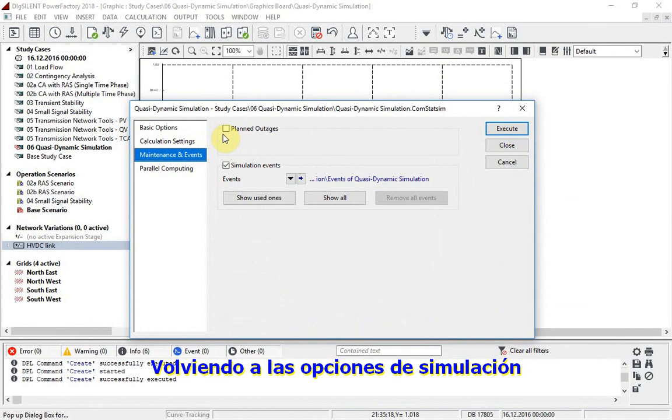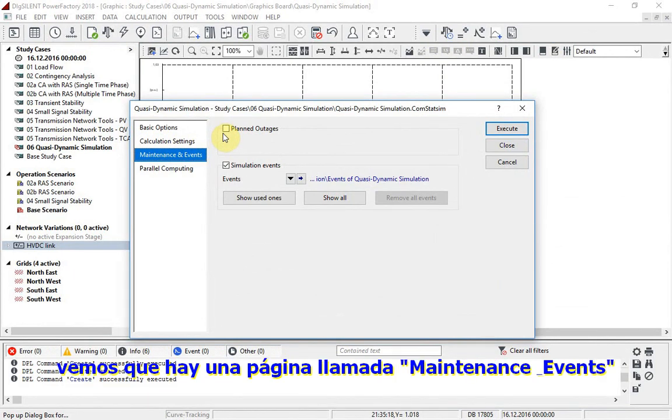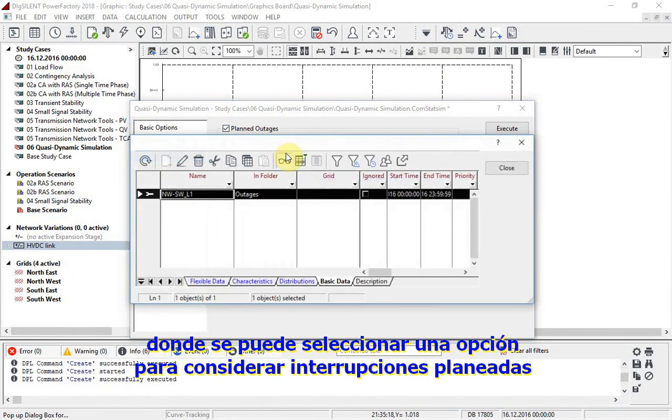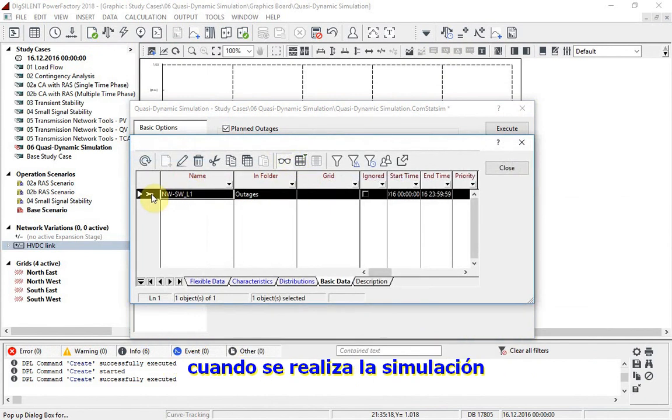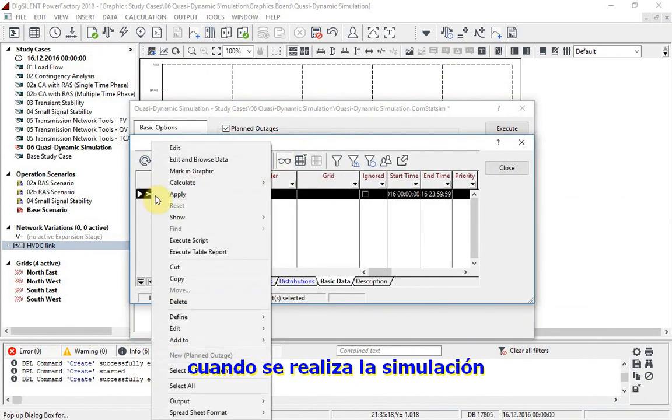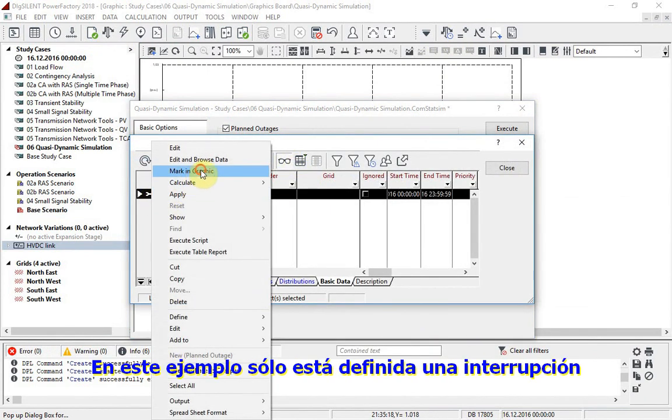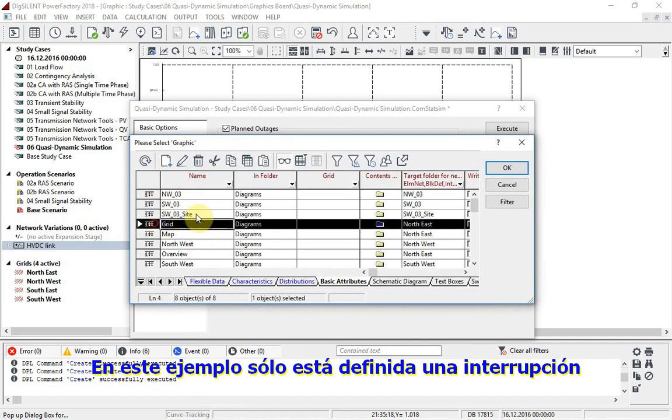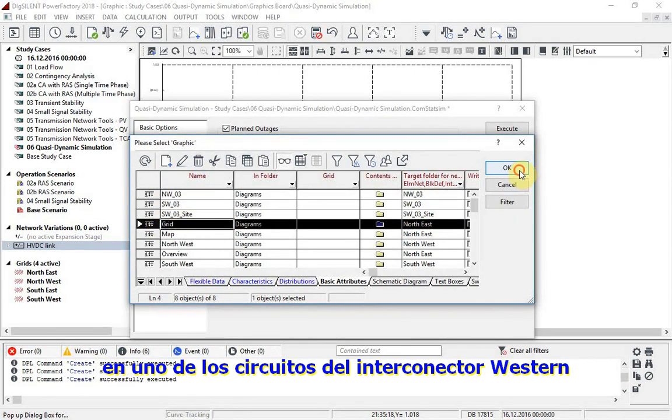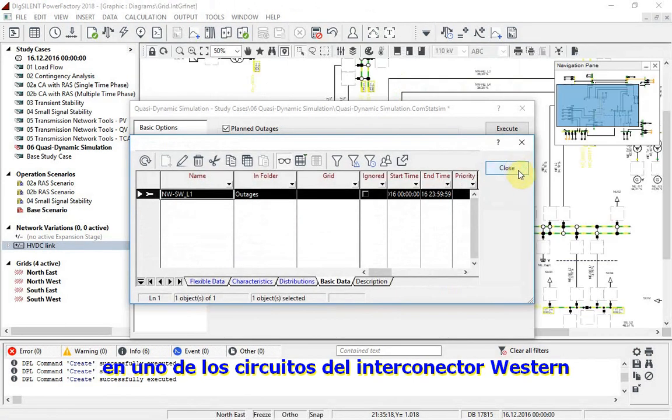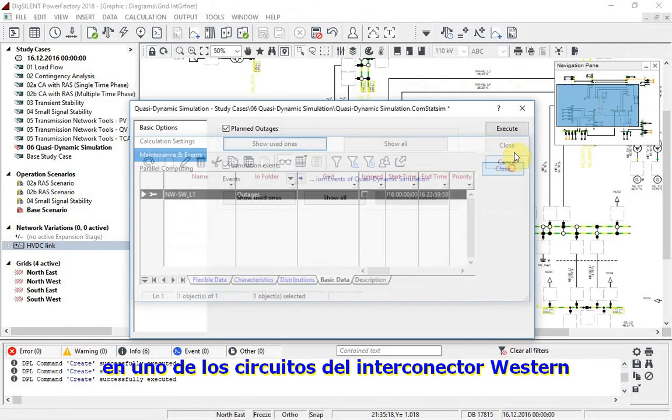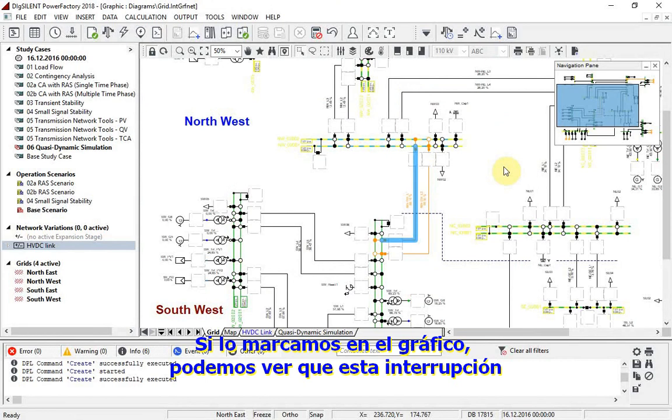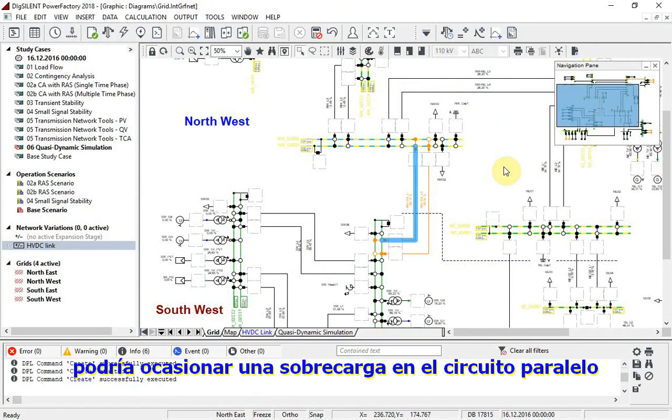Returning to the simulation options, we see that there is a page called Maintenance and Events, where an option can be selected to consider planned outages when running the simulation. In this example, just one outage is defined, on one of the western interconnector circuits. If this is marked in graphic, we can see that this outage may result in overloading on the parallel circuit.